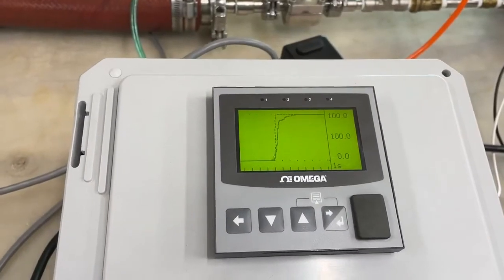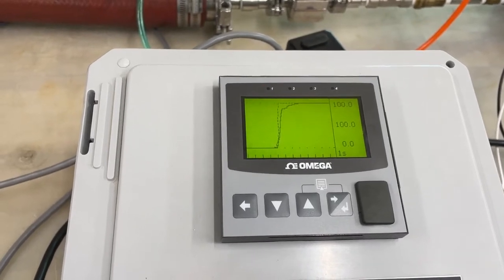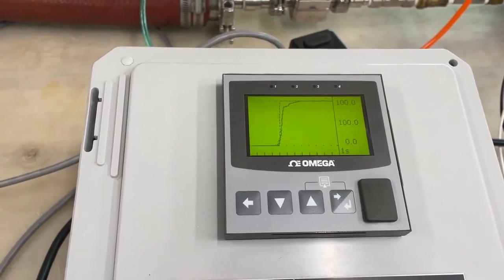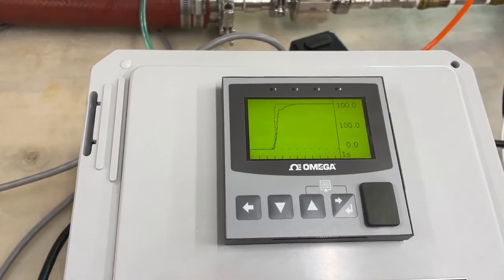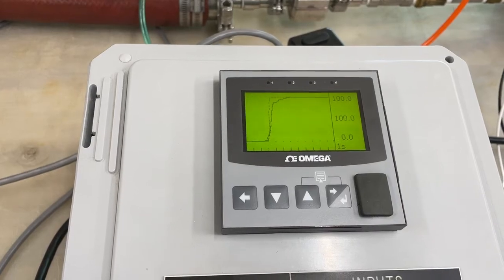Now the flow is at 100% set point or 1000 grams per minute. You can see how the PID loop adjusted the pressure on the dome to achieve the correct flow and with our Equilibar flow control valve and this PLC setup we have achieved a 100 to 1 turn down ratio.